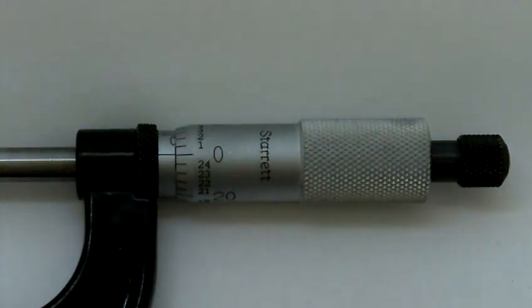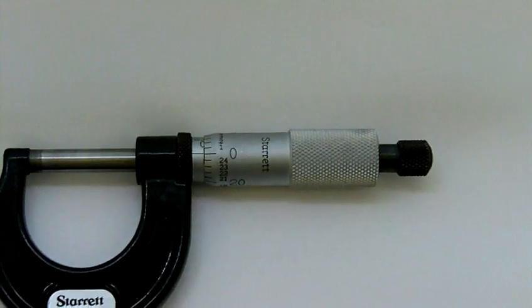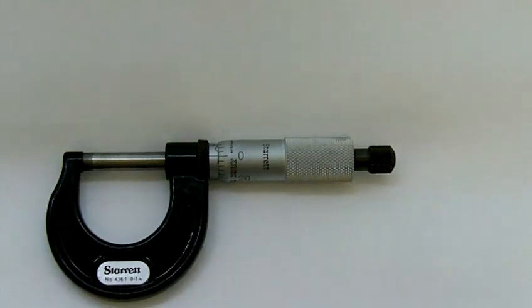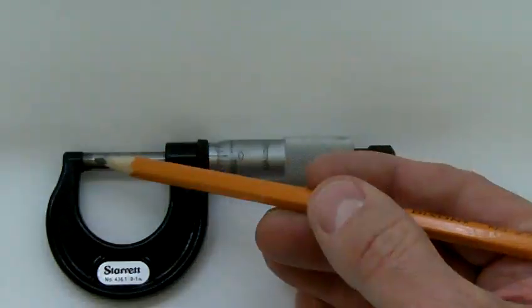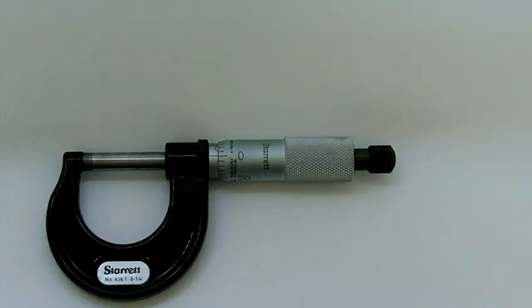Because this is a zero to one inch micrometer, the anvil and the spindle are going to touch each other. Any micrometer will have a range of one inch, so zero to one, one to two, two to three, or 25 millimeters. Zero to 25 millimeter where the anvil and spindle will touch, 25 to 50 millimeters where they will be apart.